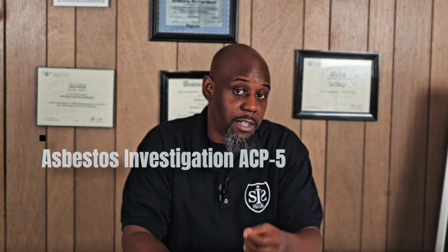Usually we will have to get an asbestos investigator to go out to the building and take samples to see if there's any asbestos in the building, or to see if we can or cannot work in any particular area. After the engineer gathers up all those documents, the final thing is to pay the fire department filing fees. Whatever those filing fees are is usually generated at the end of the process. Pay those filing fees. The engineer will then submit that paperwork to the fire department. Then the next step after that will be the plan review.